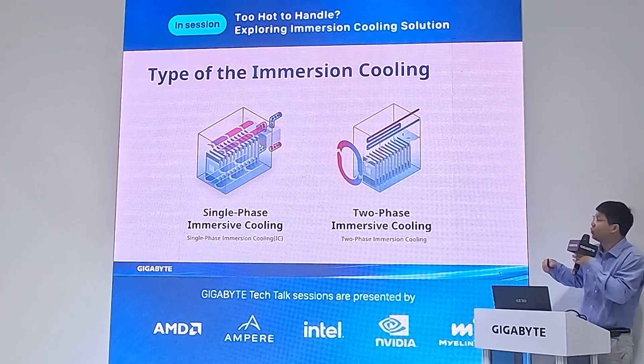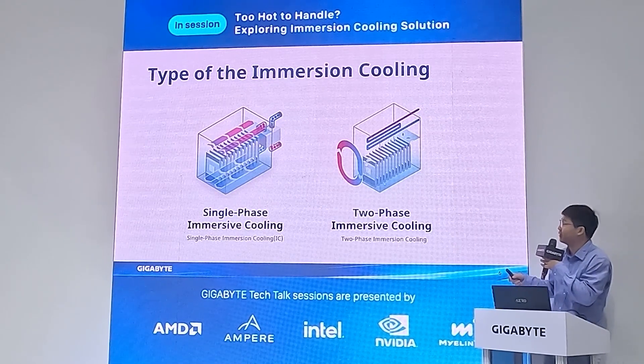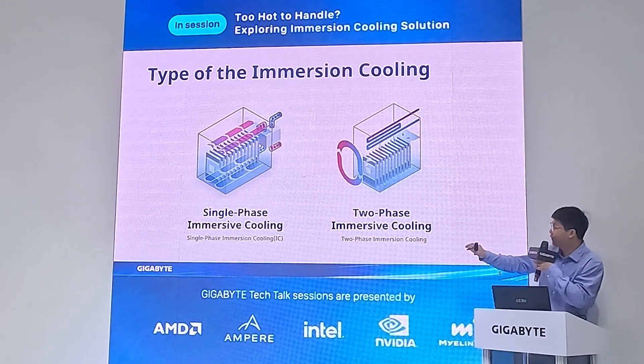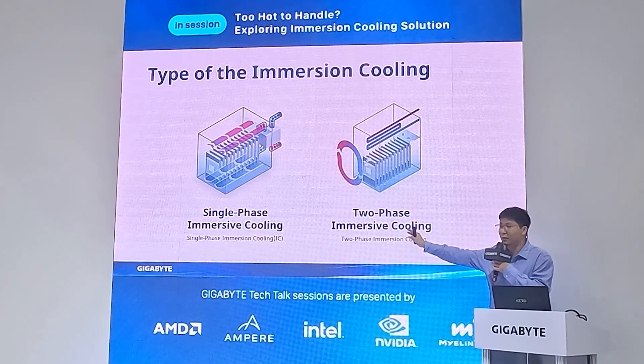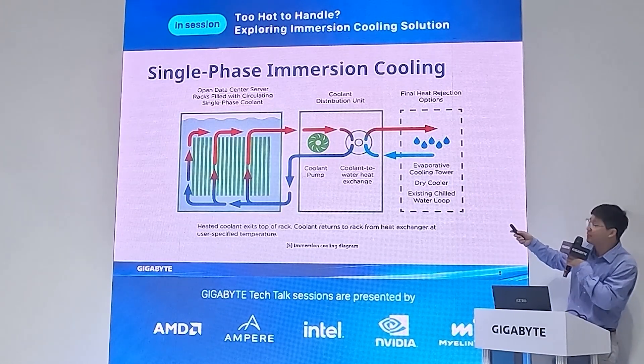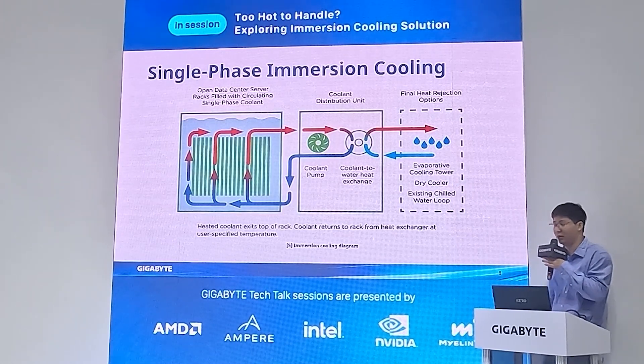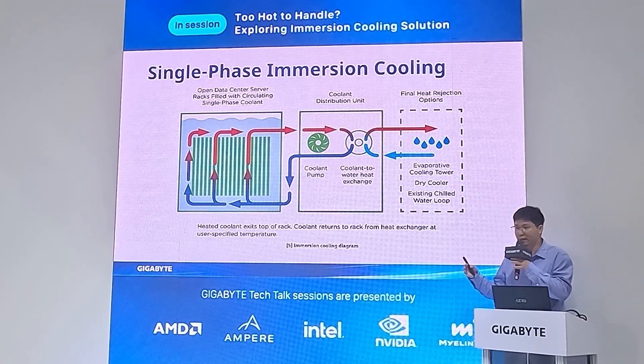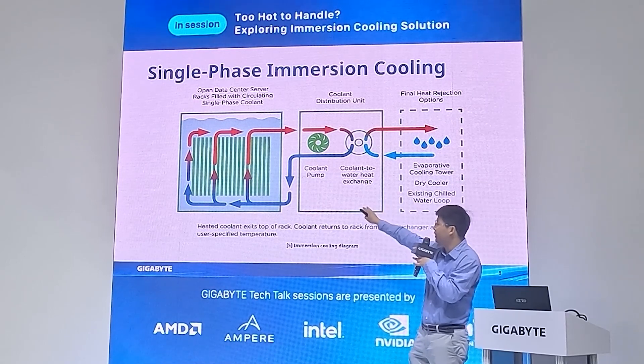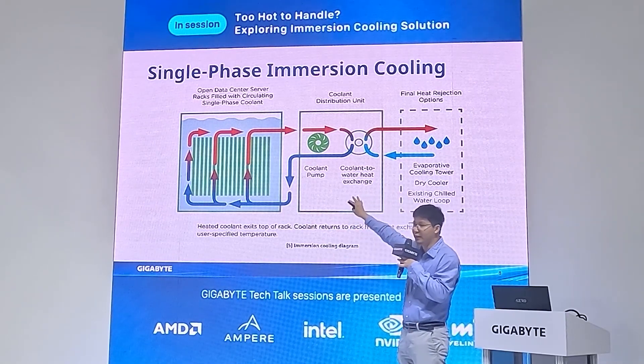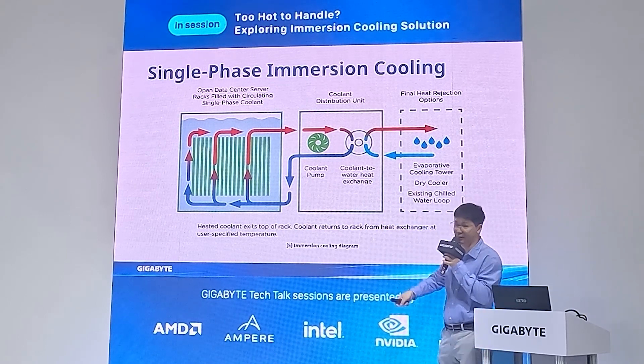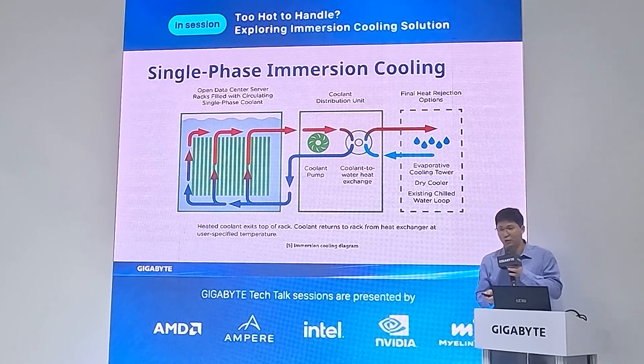Looking at the market, there are currently two types of immersion cooling: one-phase and two-phase. Starting with one-phase immersion cooling — the principle involves immersing the whole server into a tank. A cooling distribution unit connects between the tank and the cooling tower, performing heat exchange and bringing heat back to the cooling tower for dissipation.